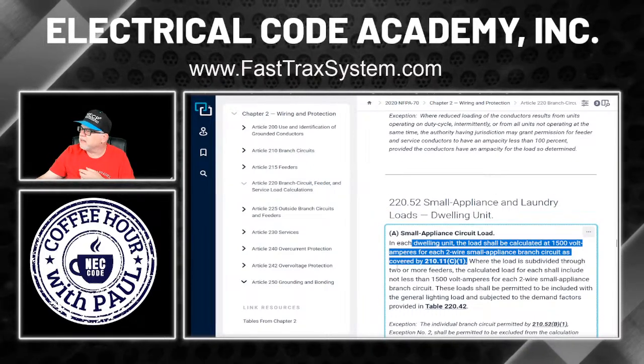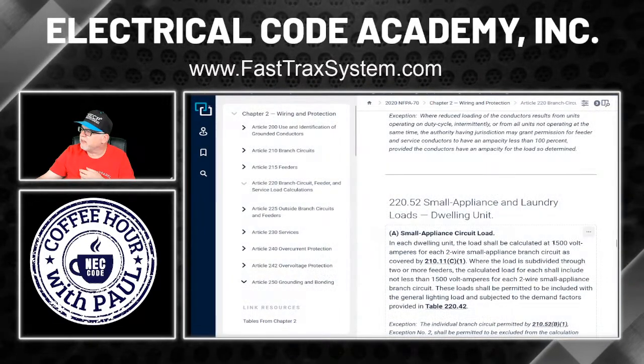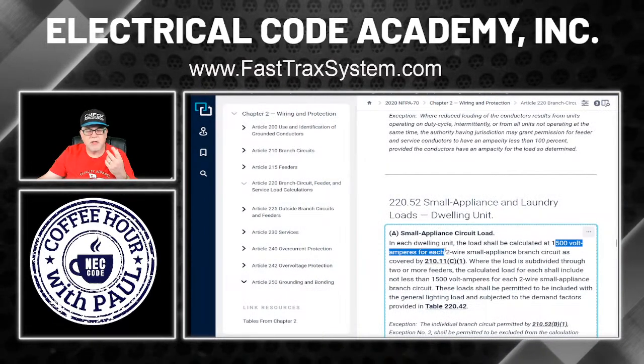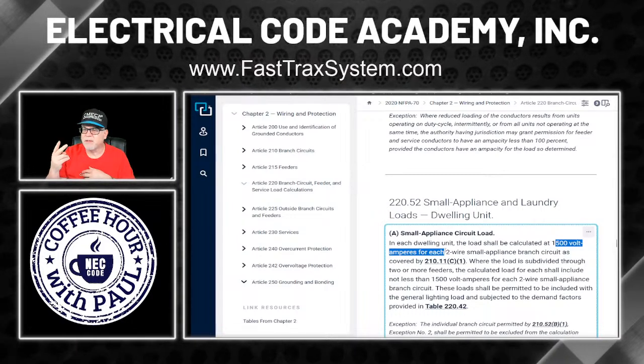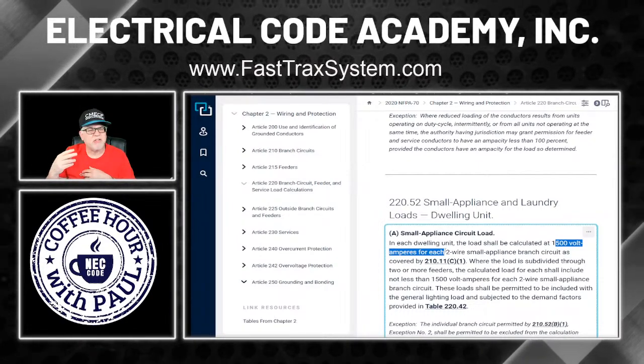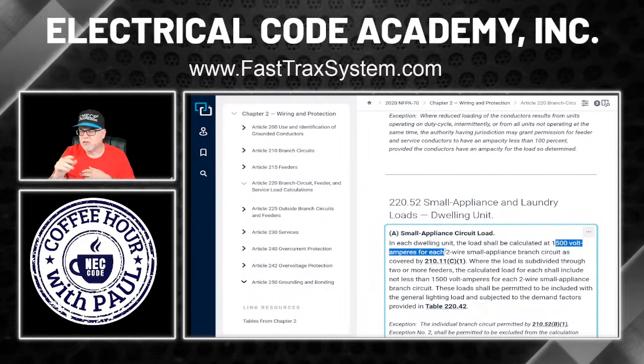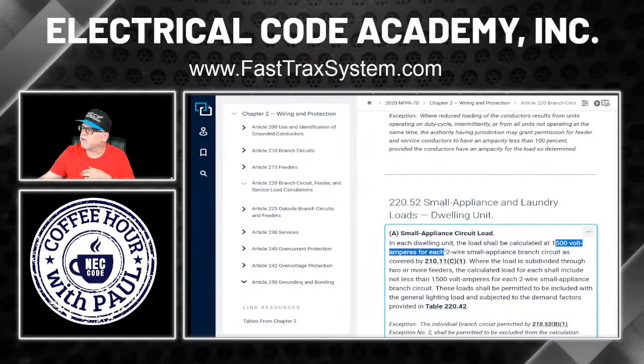And it tells me that they are what? 1500 VA each, right? So we have to have a minimum of 2. So that's 1,500, that's 3,000 right there just for the two 1,500 small appliance branch circuits, okay?